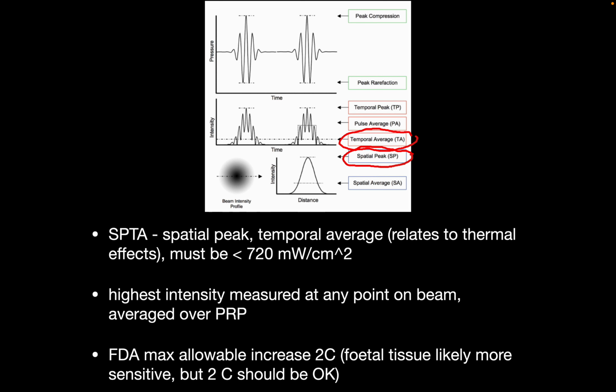and that this relates to thermal effects, and it must be less than 720 milliwatts per centimeter squared. So what it means is that it's the highest intensity that's measured at any point on the beam, and then they average it over the pulse repetition period. There are FDA standards, of course, for ultrasound usage, and the maximum allowable increase is 2 degrees Celsius.